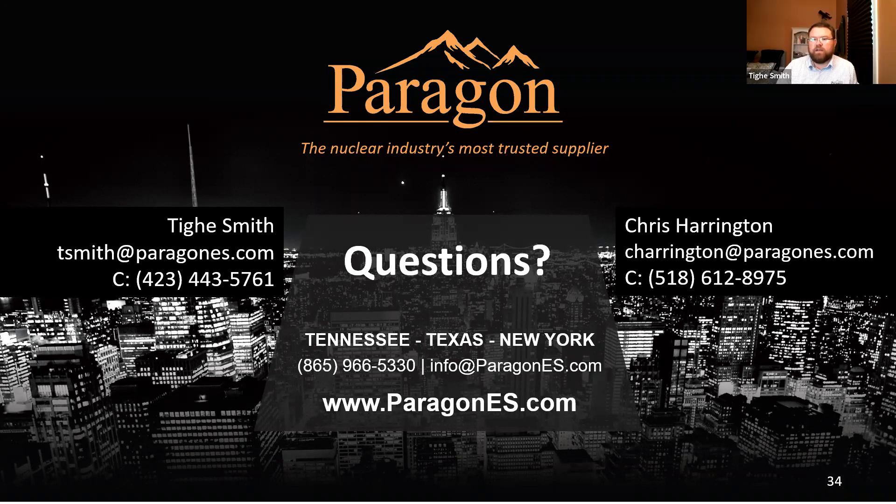Do we have any experience at Paragon doing software repairs or are we only doing hardware repairs? We've done a little bit of both. When we consider a software repair, we've seen instances where maybe an EEPROM chip has one gold standard one that keeps getting moved from board to board. If we can get a handle on that one EEPROM chip, and if it's not locked, we'll be able to record all the information on that chip and then be able to replicate it on subsequent EEPROMs. Outside of that, if it's some kind of embedded firmware, that's where it really becomes challenging — it's not something we've had to do at this point. We have also done CPLD type chip replacements.